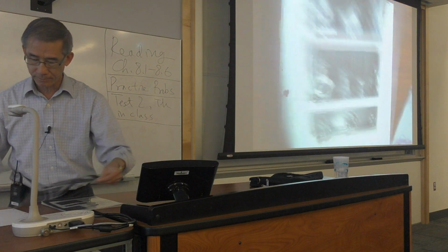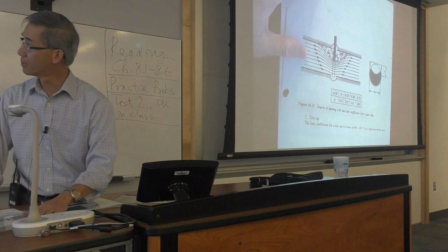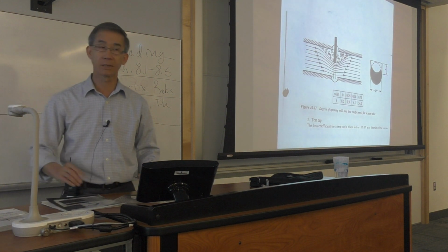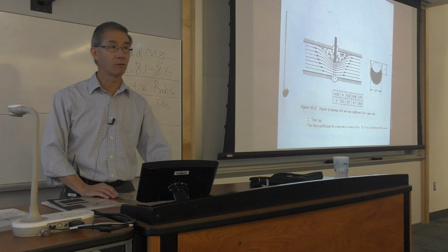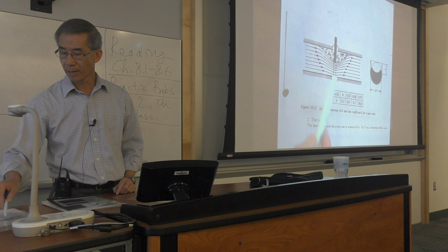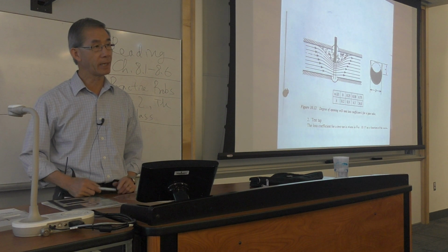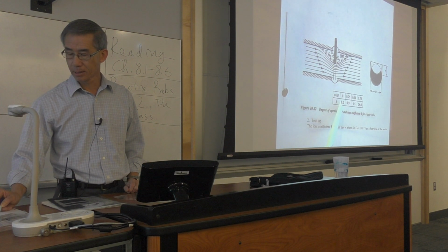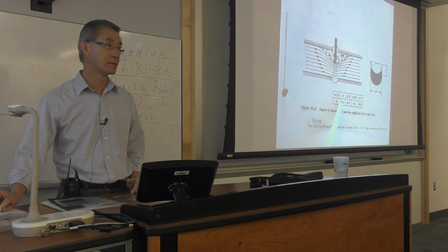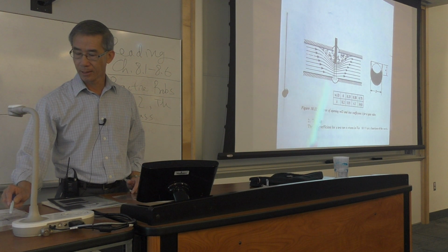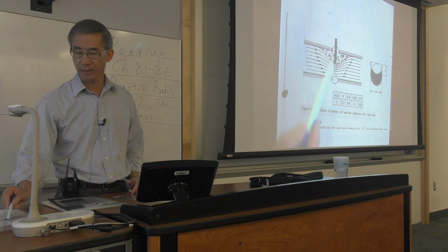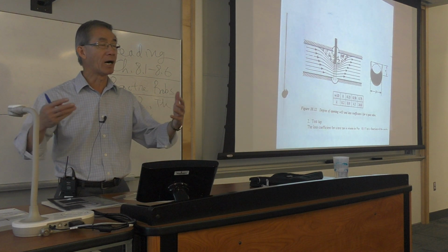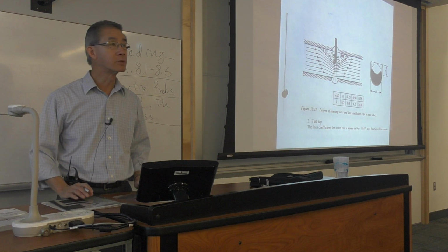The manufacturer of all of these will have to do tests, and from that they give you the kind of table you use for your homework. So here's a gate valve, partially open, and you have different values of K, the loss coefficient, depending on the position of the valve. When it's fully open, there's very little loss, a K of about 0.2, created by some cavity in the valve that allows it to open and close.